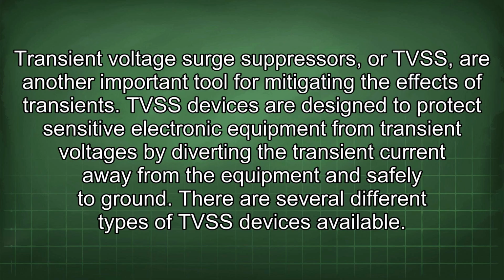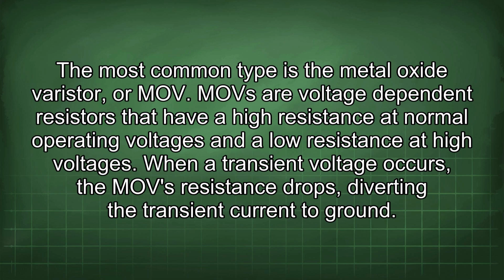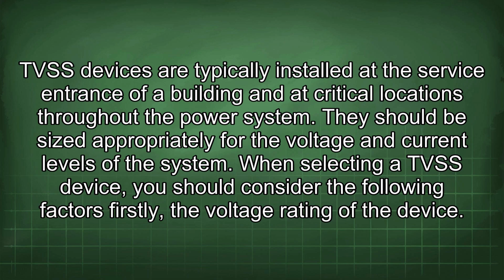Transient voltage surge suppressors, or TVSS, are another important tool for mitigating the effects of transients. TVSS devices are designed to protect sensitive electronic equipment from transient voltages by diverting the transient current away from the equipment and safely to ground. There are several different types of TVSS devices available. The most common type is the metal oxide varistor, or MOV. MOVs are voltage-dependent resistors that have a high resistance at normal operating voltages and a low resistance at high voltages. When a transient voltage occurs, the MOV resistance drops, diverting the transient current to ground. TVSS devices are typically installed at the service entrance of a building and at critical locations throughout the power system.